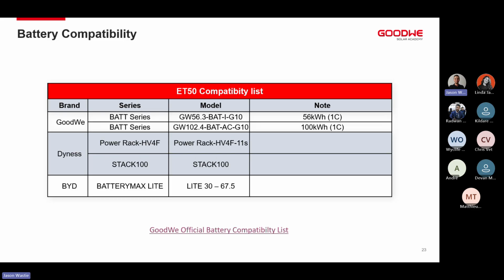On the Type A international list, GoodWe takes an inverter and gives it to BYD, BYD takes a battery and gives it to GoodWe, and we cross-match the protocol from both sides, both R&D teams, to allow the protocol to be 100% matched. The second way is our local way. With local batteries like Lithium Battery South Africa, LBSA, for example, we took an inverter and gave it to the team at LBSA. We gave them our default high voltage battery protocol and said, this is our inverter, this is the protocol, and their R&D team matched their battery firmware and battery protocol to the GoodWe default protocol.